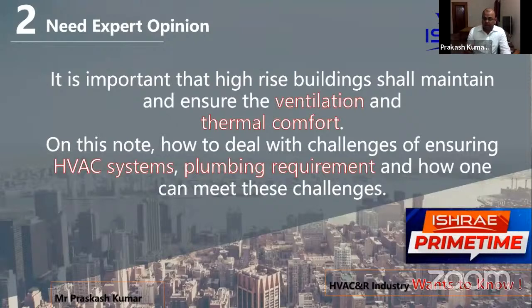What happened is that our toilet exhaust fan stopped working, and the fresh air fan continued working. Three of the floors complained that their glass panels had broken, because you are supplying air and not sucking it out, so you are creating a pressurized system on different floors. Two or three floors, I remember, complained that their glass had broken all of a sudden. Normally a rise of 3 to 4 mm of pressure in the air, human beings don't feel it, but glass or other things which are not designed for that pressure break.